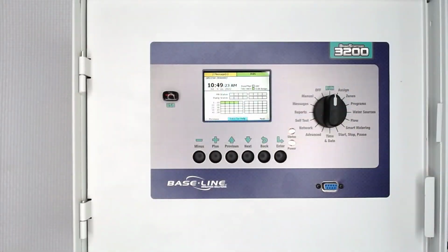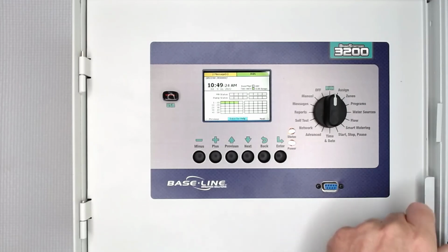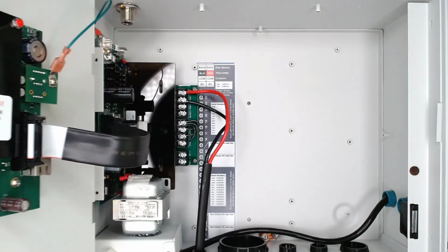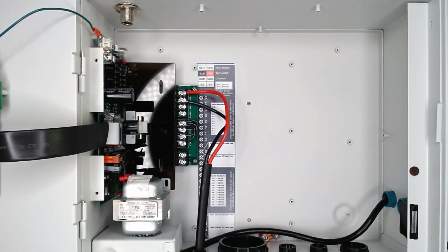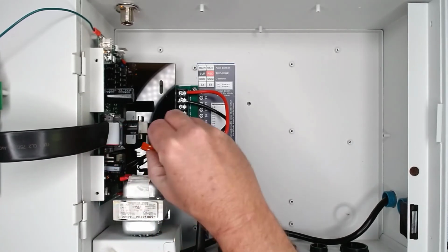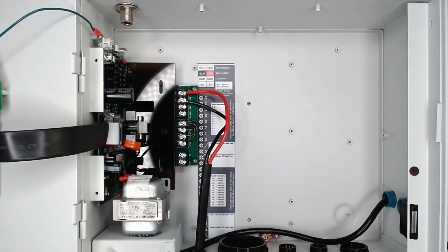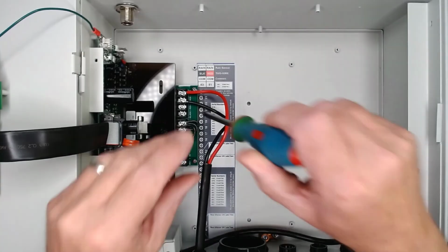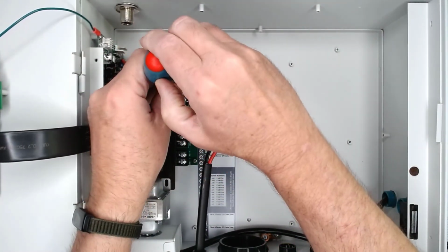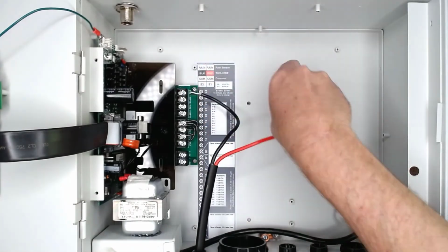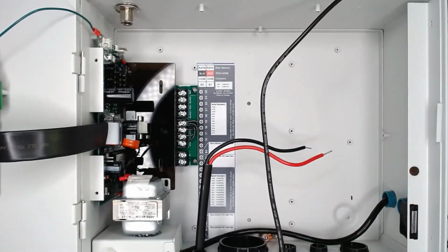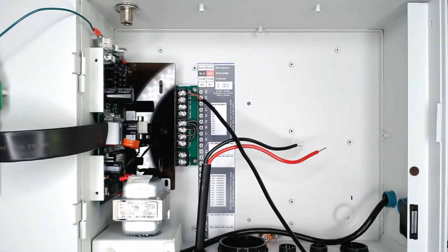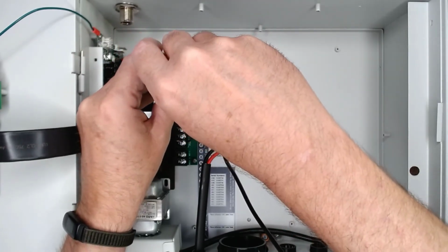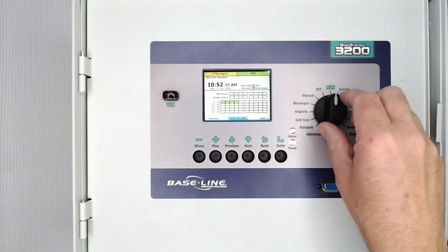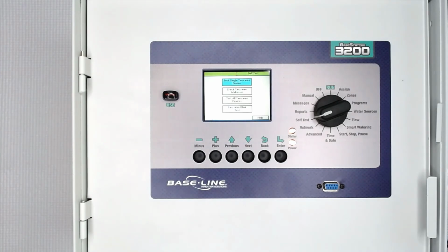Now let's go test the device back at the controller. Anytime you work on the two-wire path, power down the controller. Unplugging the controller, turning off the circuit breaker, or disconnecting the orange plug on the control board all can power down the controller. With the power off, I can disconnect the existing two-wire path from the terminals and set those aside. I'll connect the soil moisture sensor to the red and black two-wire terminals, making it the only wire connected to the controller. Power the controller back up and return to the self-test menu, looking for that same device again.